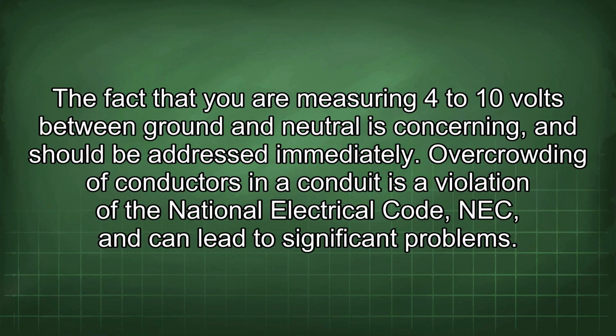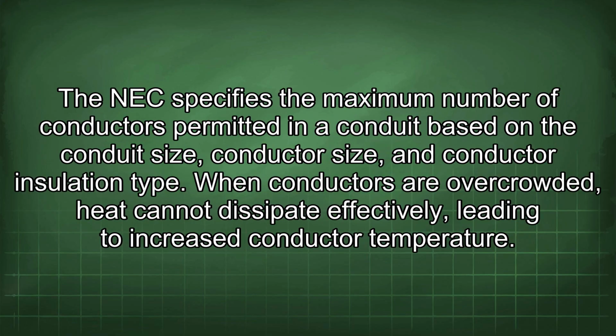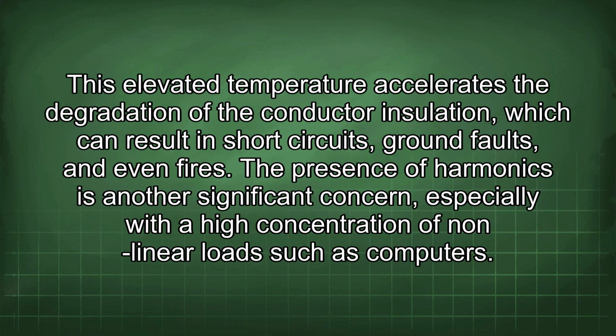The fact that you are measuring 4 to 10 volts between ground and neutral is concerning and should be addressed immediately. Overcrowding of conductors in a conduit is a violation of the National Electrical Code (NEC) and can lead to significant problems. The NEC specifies the maximum number of conductors permitted in a conduit based on the conduit size, conductor size, and conductor insulation type. When conductors are overcrowded, heat cannot dissipate effectively, leading to increased conductor temperature. This elevated temperature accelerates the degradation of the conductor insulation, which can result in short circuits, ground faults, and even fires.